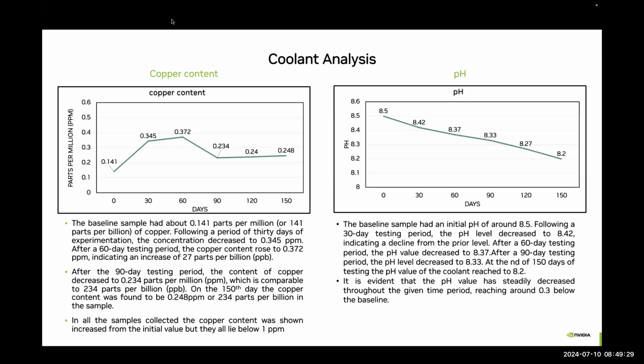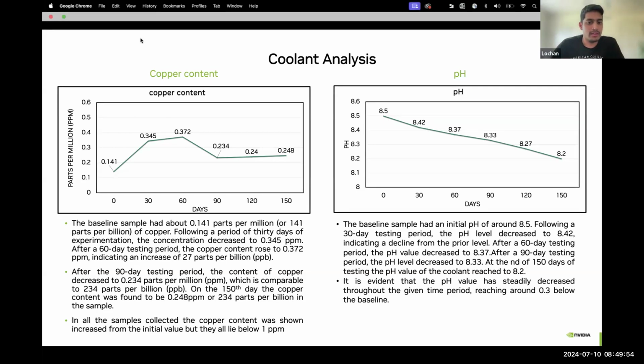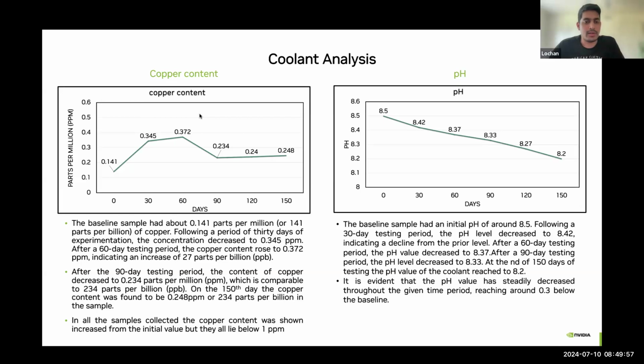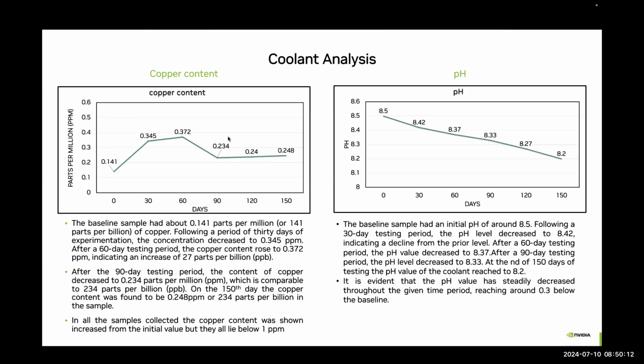So 45 was our inlet for the coolant. And for the copper content, what we are currently assuming is that the drop could be due to the inhibitors present in the fluid. Maybe the inhibitor started acting after some particular point of time. We are not sure what other inhibitors were present. The vendor never disclosed the different corrosion inhibitors except for the tolyltriazole levels. So we are only aware of the tolyltriazole levels over the period of 150 days, but we are not sure how the different corrosion inhibitors in the liquid were acting over a period of time during this test. And what is the liquid name?